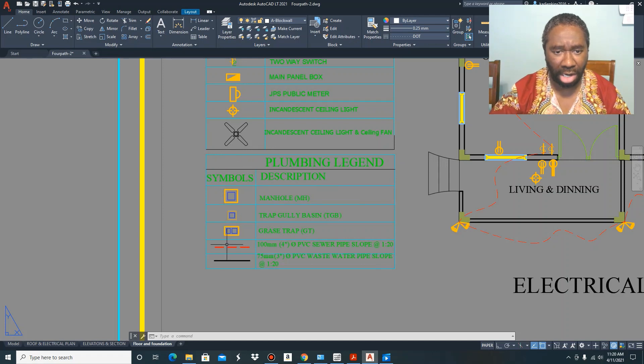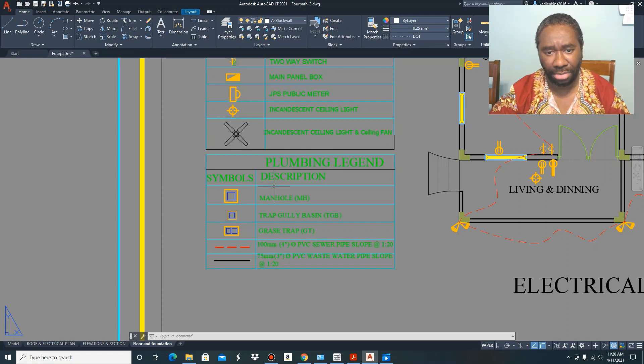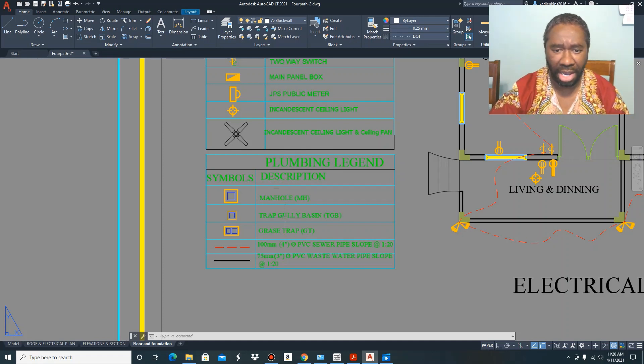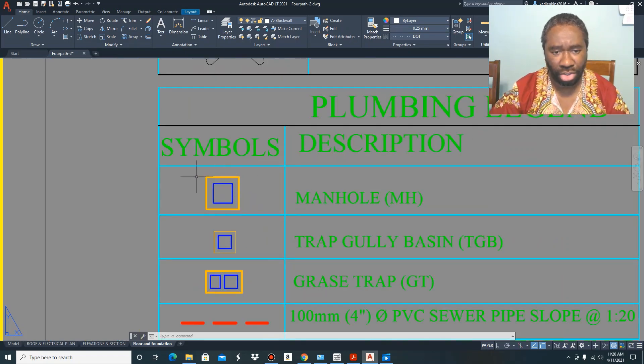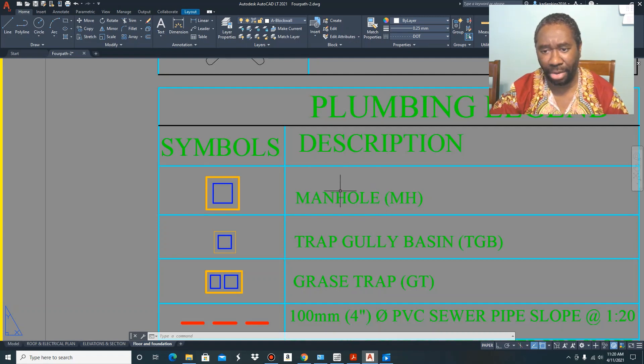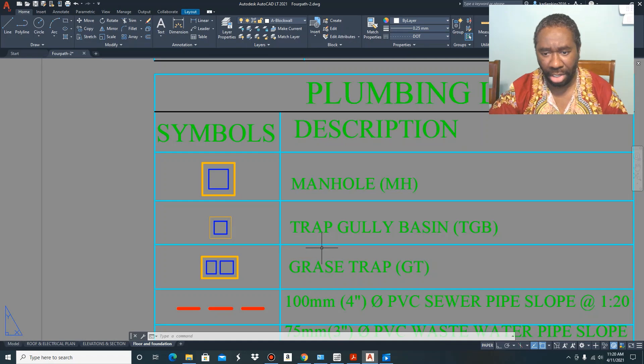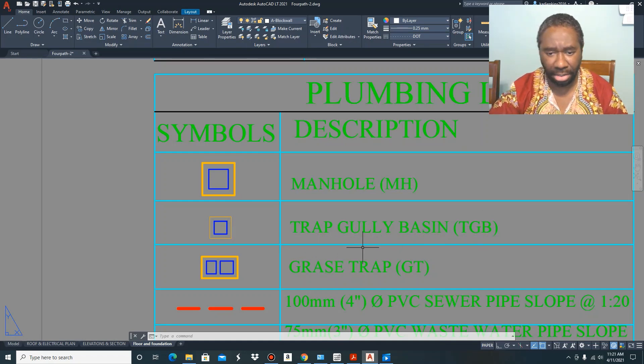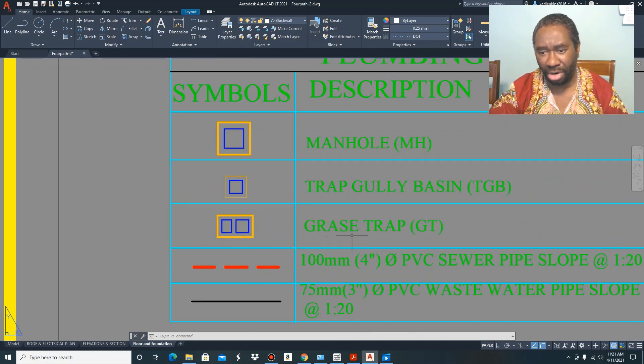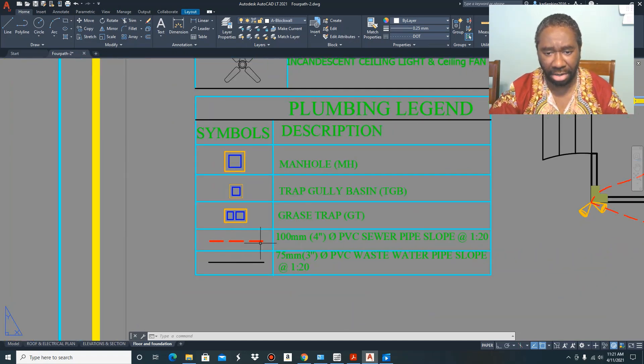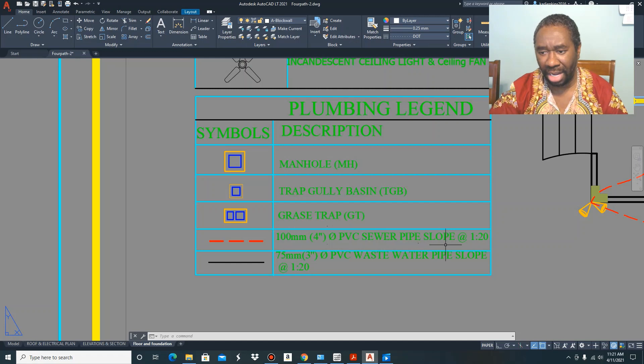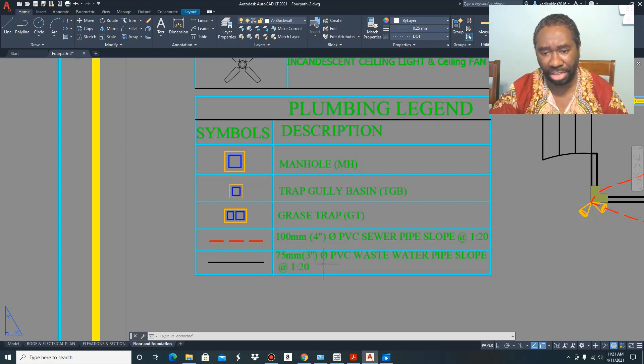In one column we have the symbols, and in the column to the right we have the description. This square here represents the manhole or MH as you might see it on the plan. The smaller square is for the trap gully basin or TGB. This rectangle is for the grease trap or GT. This broken line is for the 100 millimeter (four inches in diameter) PVC sewer pipe at a slope of 1 in 20, and this solid line is for the 75 millimeter (three inches in diameter) PVC wastewater pipe at a slope of 1 in 20.